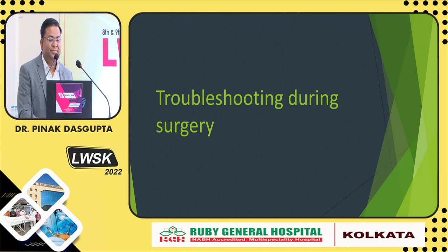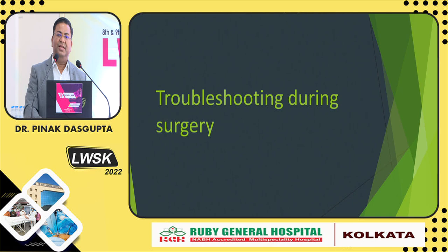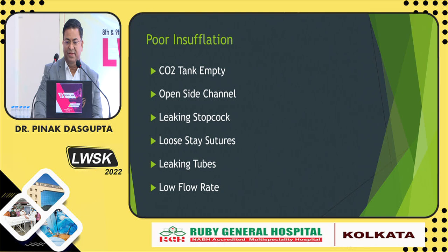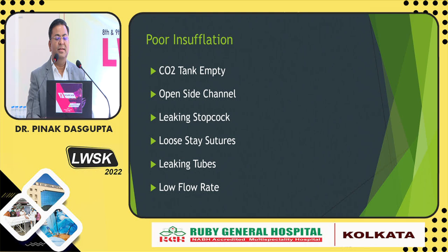One should be aware that if certain problems come up, where exactly the problem lies. So if there is poor insufflation, you are unable to achieve adequate pressure, or the abdomen is not getting distended, then what could be the reason? One should check systematically, running through the possible causes.